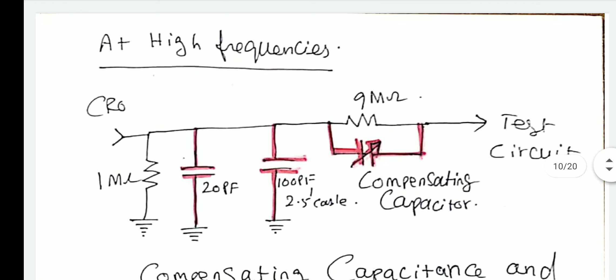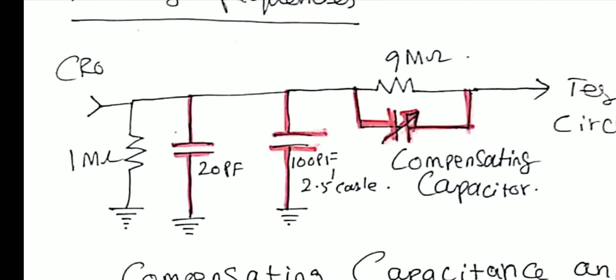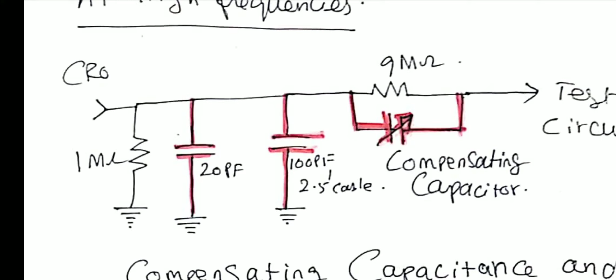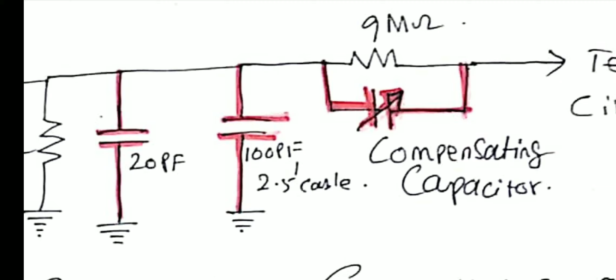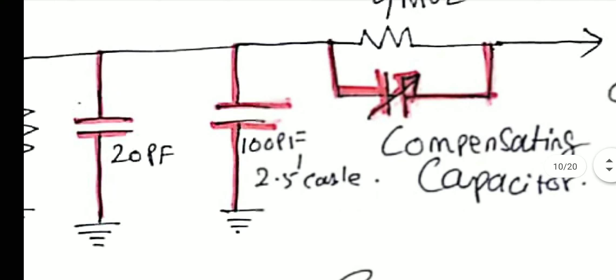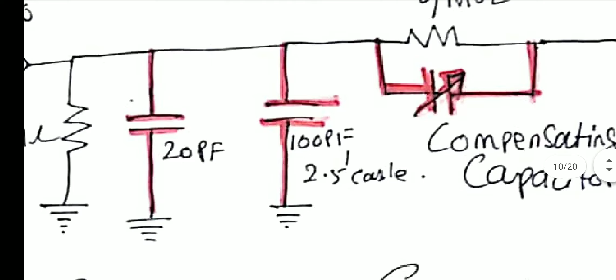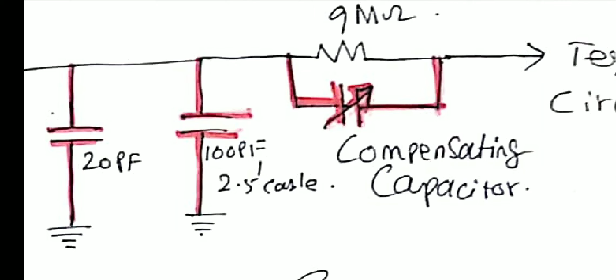But at high frequency, resistance will not come into the picture, only capacitance comes into the picture. So when you connect the test circuit with the CRO, when the high frequency signal comes from the test circuit, it flows through the capacitive path, shown in red color here. So what happens, these capacitors come in parallel, 20 picofarad and 100 picofarad. This 100 picofarad is the capacitance of the cable, approximately a 2.5 feet cable; for 1 feet it's 30 picofarad, for 2.5 feet it's 100 picofarad. So this 100 picofarad is the cable's inherent capacitance. This 20 picofarad is the input capacitance of the CRO, and this is the capacitance we have connected, the compensating capacitance.